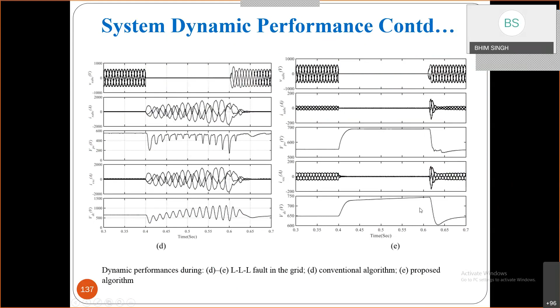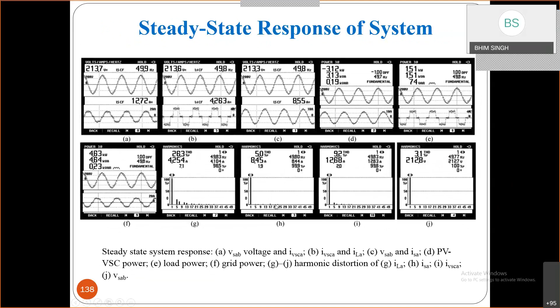And you can see even the supply current THD is only 5%. Here you can see the supply current where you are feeding a highly nonlinear load current. And the voltage THD is also reasonable, 3.1%. So we are able to meet all those requirements. The internal control signals we are able to generate well, and at night you can say it works like an active filter.